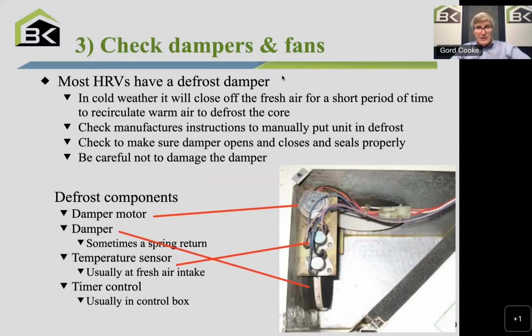The colder it gets, the more we need for defrost. So in cold weather, it closes off for a short period of time to recirculate. Most manufacturers will show you how to put the unit into manual defrost, just so you can see that it's operating correctly. But you do want to make sure the damper opens and closes and seals properly.